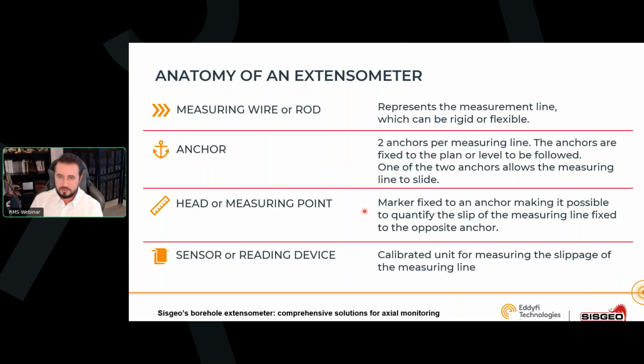Then you can see there are 4 main parts in an extensometer. So these 4 main parts are the measuring wire or the measuring rod. Each represents the measuring line. It can be rigid or flexible. The anchor, so you have per measuring line 2 anchors, proximal, distal. So these anchors are fixed into the plan or the level to be followed. So one of the 2 anchors allow the measuring line to slide. So one is fixed and attached to the line. The other one has to welcome the line and to let it slip. It has to be mobile, very important.